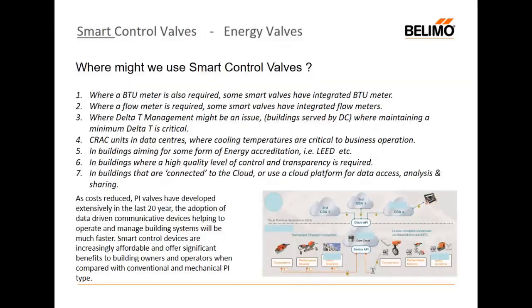So where might we use a smart valve now? A smart valve is a valve which I would consider has some commonalities. I just want to talk about where we might use them, and then let's think about what they should do. Where I have a requirement for a BTU meter as well as a control valve, some smart valves have integrated BTU meters because they're measuring the flow and the temperatures. So essentially they know the cooling energy. Where a flow meter is required, smart valves should, if they're very good, have a flow meter. So we don't need to buy a flow meter and a control valve. It's there in a single unit.